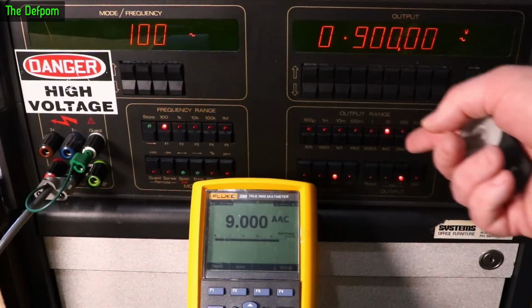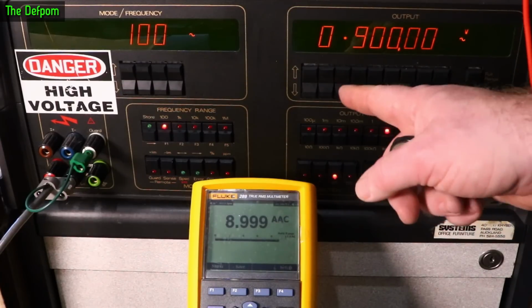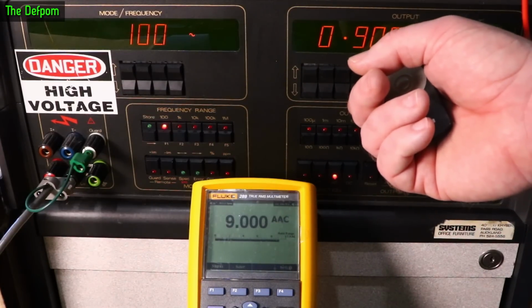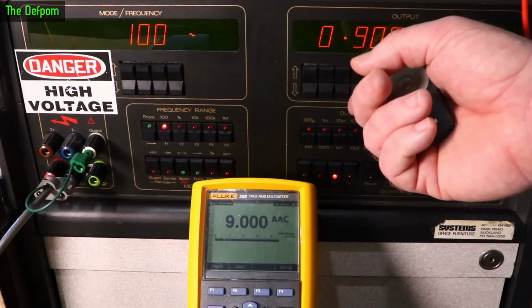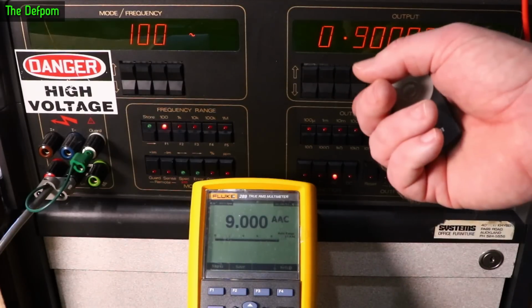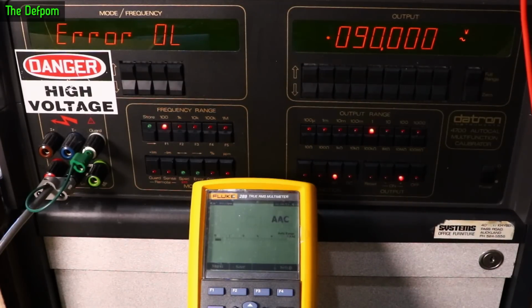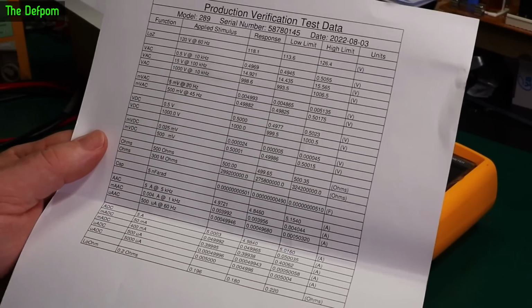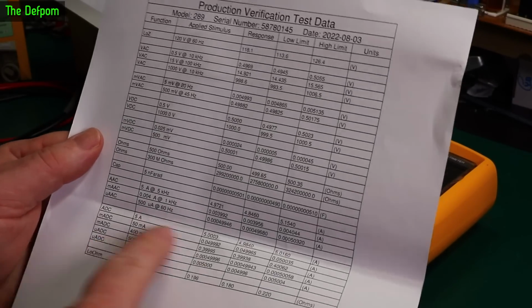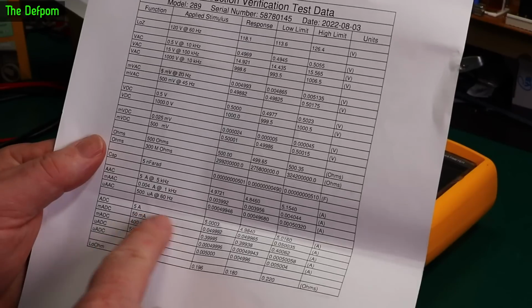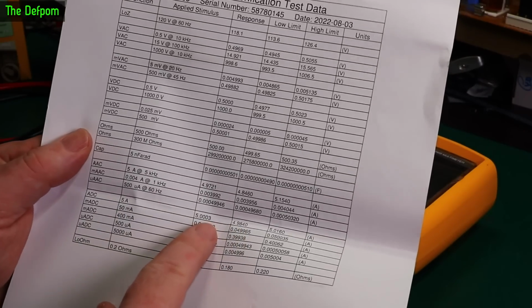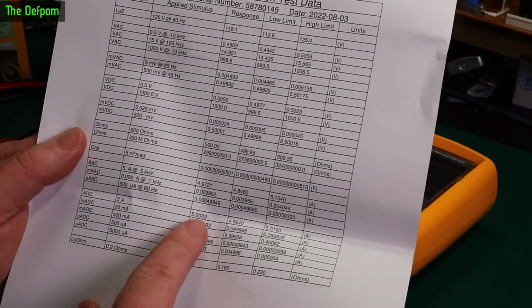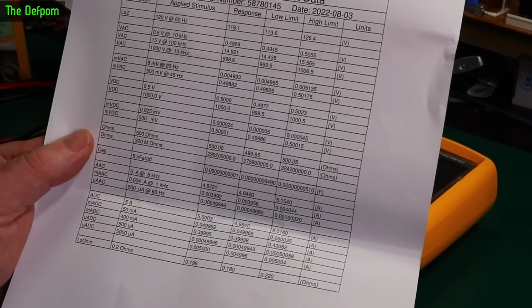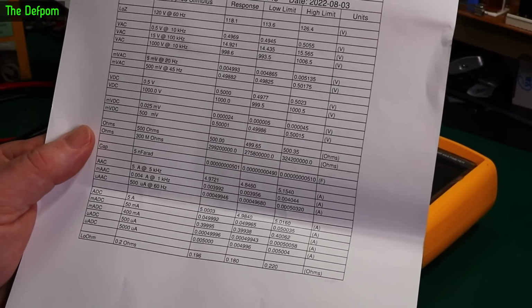Right, so there we go. 9 amps AC, absolutely fine. Now I'm getting the error. Overload errors. So yes, it's not liking it for some reason. I meant to look at this whilst I was doing the calibration checks on the calibrator. Anyway, I completely forgot. But one of the recent ones is the amps DC, 5 amps, which we just did. And remember, we were reading a few counts high, and sure enough, at 5 amps we are reading a few counts high. So it does correlate, at least in that regard.